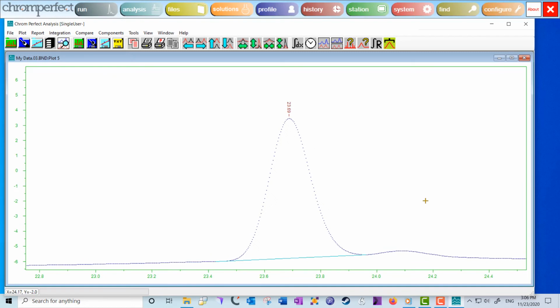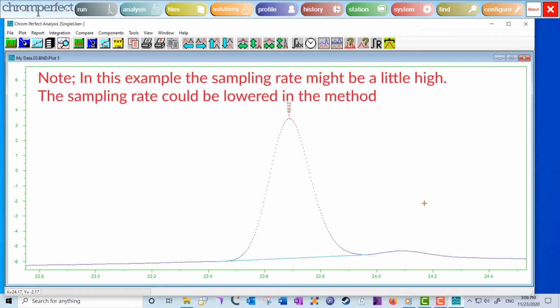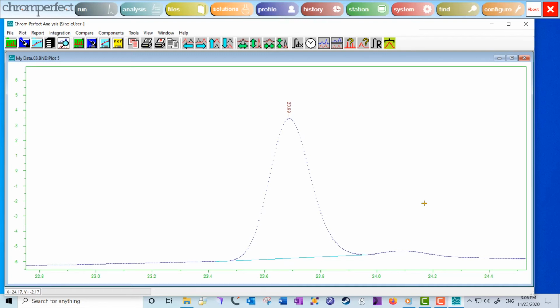Roughly count the data points across one of the narrowest peaks. There is little need to have more than 30 dots across the peak. If there are less than 10, then you should go back, open your method file, and increase the sampling rate, then save the method file. This will affect future raw files, but not those already collected. You may wish to collect another set of raw files before proceeding here, but that may not be necessary. Unless the sampling rate is very low, you can forge ahead with the file you have.